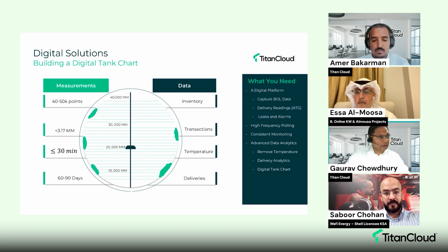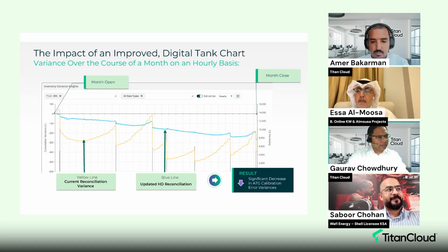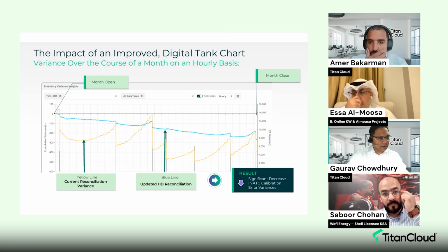Now, given how the tank is exercised, the process can take anywhere between 60 to 90 days, and we can calibrate a tank. What is the impact of that? If I go to the next slide, the impact is in the variances, and we can push the tank chart, or the strapping chart, to a gauge as well, so that you see the impacts. In this example, if the data was coming from a raw tank gauge, that is the orange line. You can see how much it fluctuates and how it's performing.